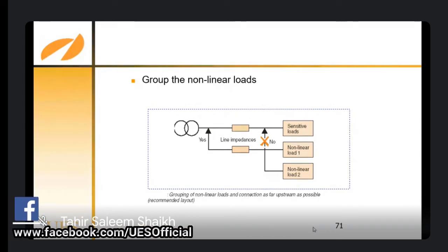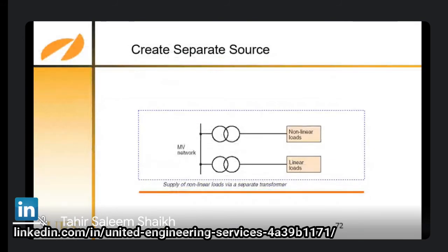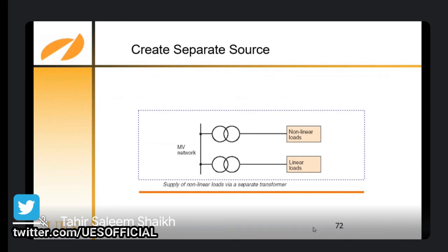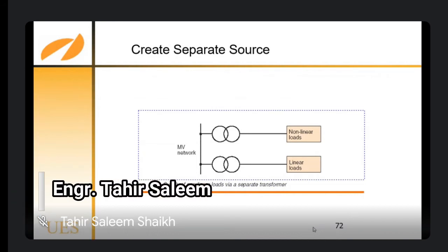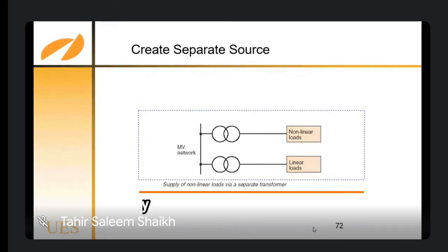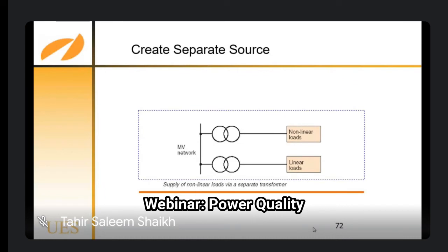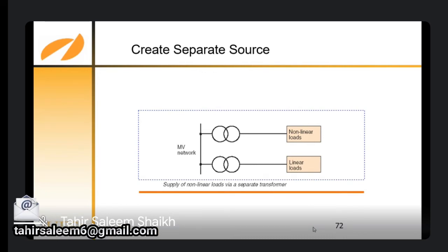There is another solution also you can see over here. If you are getting 11 kV, which in Pakistan is medium voltage, the non-linear loads and linear loads are kept separate, fed from different transformers. That will reduce the impact of the harmonics, and the return feedback of the harmonics from the non-linear loads to the power system will be reduced. This will not be fed back to the power system, destroying all other equipment. I have seen so many problems.